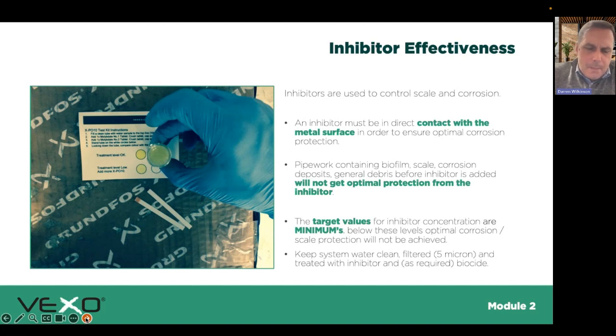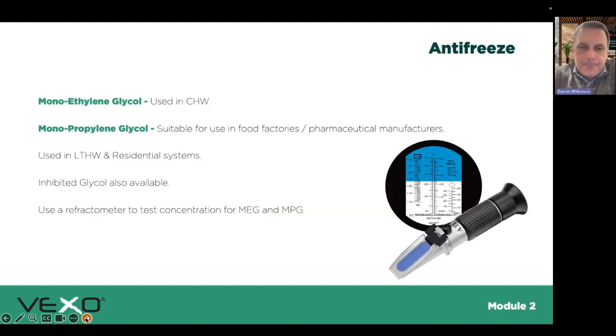I do come across sites where the water treatment contractor says there's not enough inhibitor in the system, but they hadn't consulted the manufacturer's product data sheets. Different manufacturers require different dose rates, or certain chemical compositions and items you're looking to analyze through a test kit. But keeping the right level of inhibitor is really key.